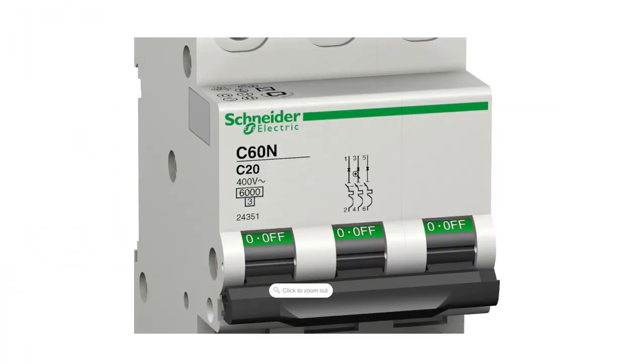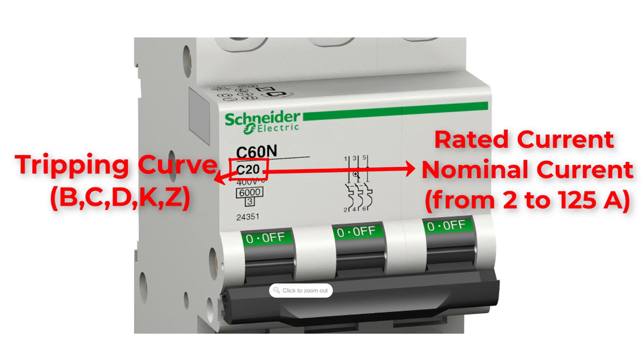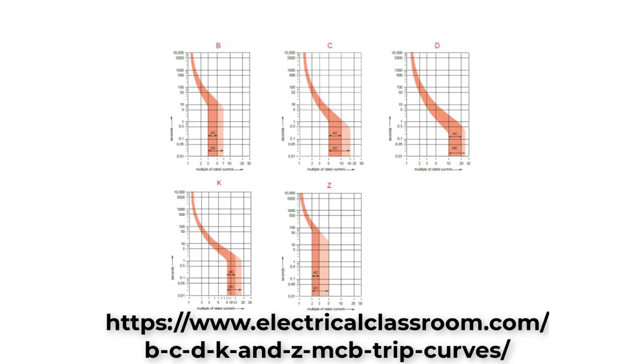Another factor here is C20. C is the tripping curve and 20 is the rated current or nominal current. We have five tripping curves: B, C, D, K, and Z. These curves describe the trip current rating of the miniature circuit breaker.